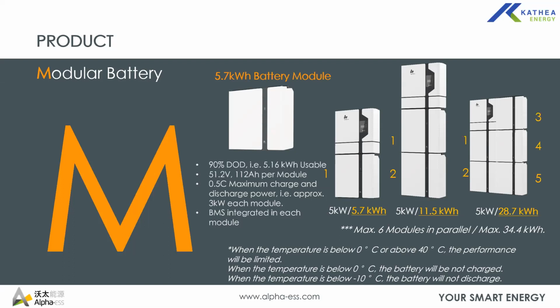It's a 48 volts with a 51.2 volt nominal voltage. And the C rating of the battery is 0.5 C. So it means the battery can only supply constant power of 50% of its capacity. We have come across this situation in most cases where someone has an Alpha system with one battery, and then when you are on UPS mode without your PV, the inverter, yes, it can supply 5 kilowatt to your loads, but the battery would limit because it has a 0.5 C rating, so it can supply almost 2.7 to 3 kilowatt of power.